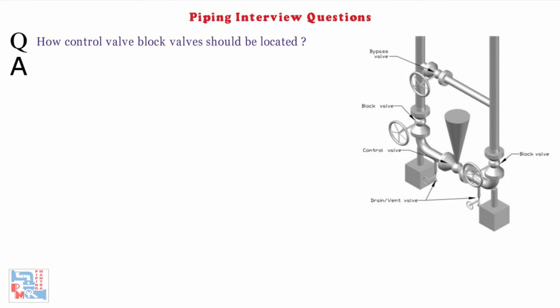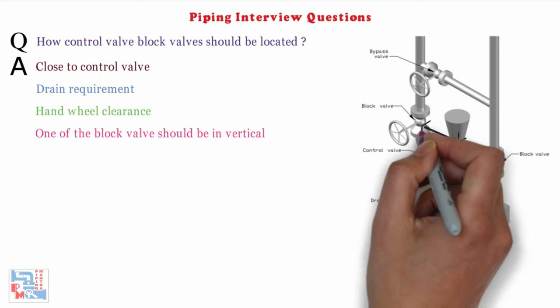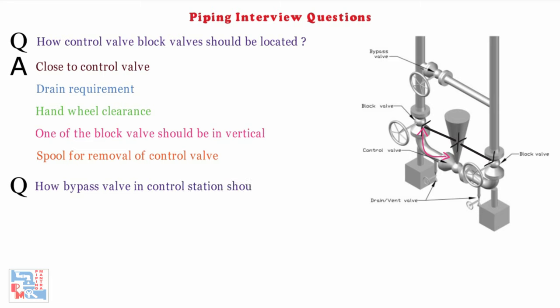Next: how should control valve block valves be located? They should be as close to the control valve as possible, considering drain requirement and handling clearance. At least one of the block valves should be placed in vertical orientation so that the spool can be removed, allowing the control valve to be removed.